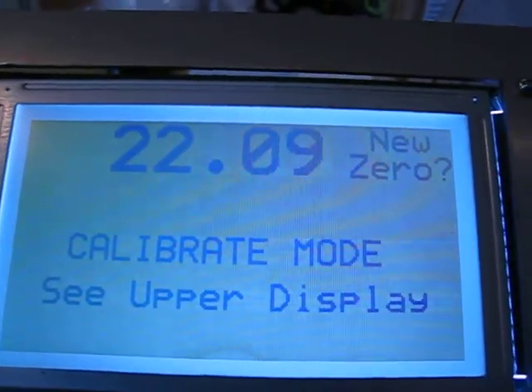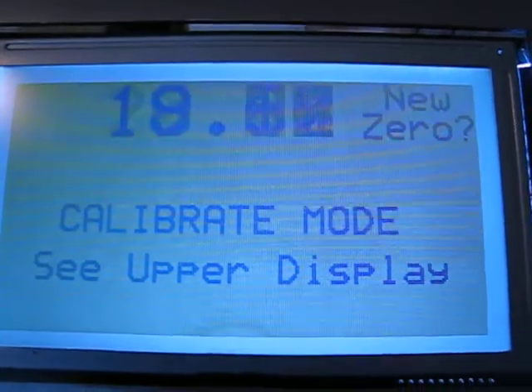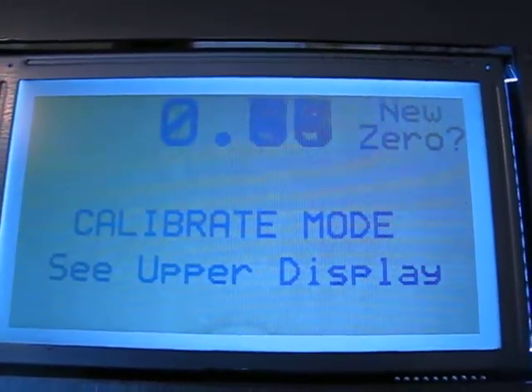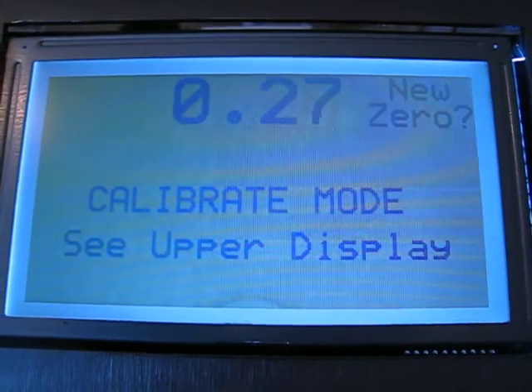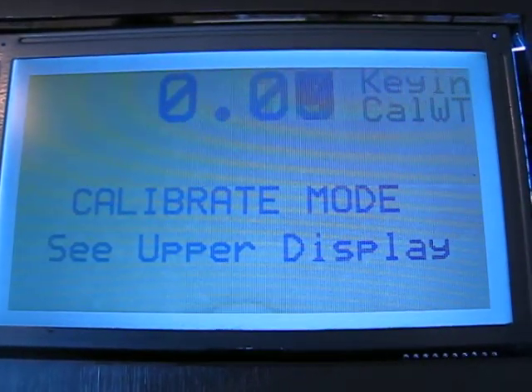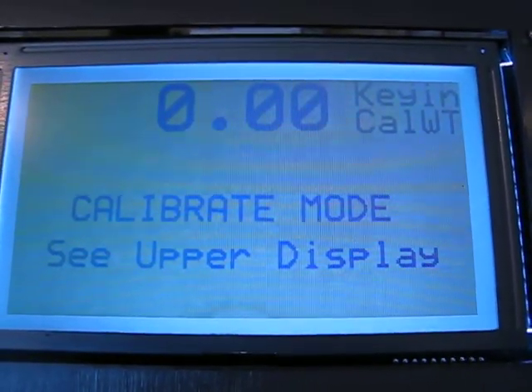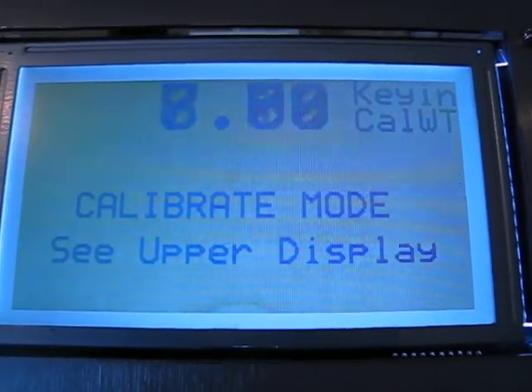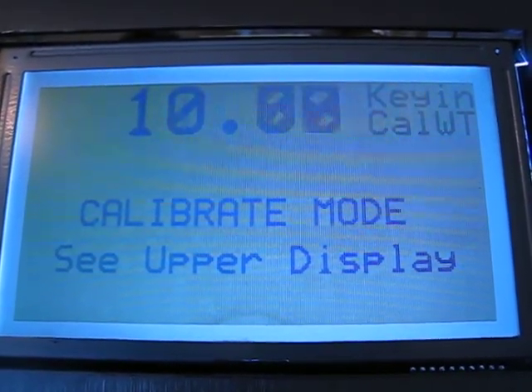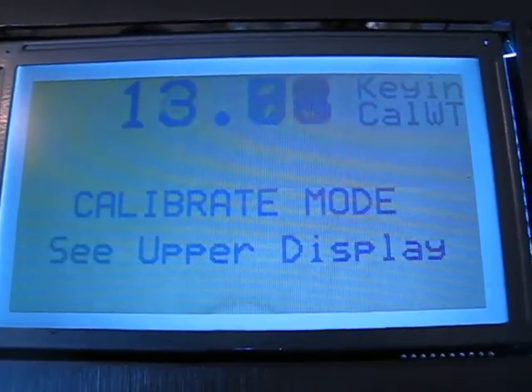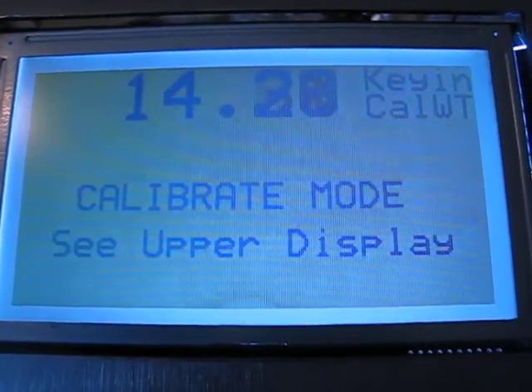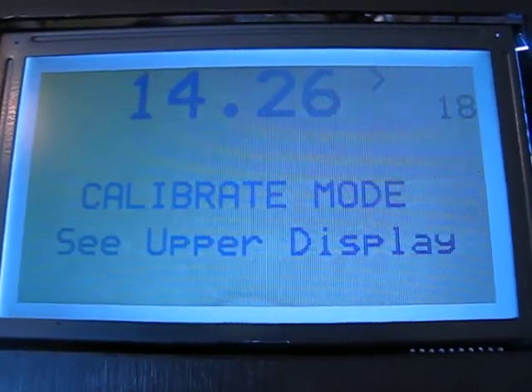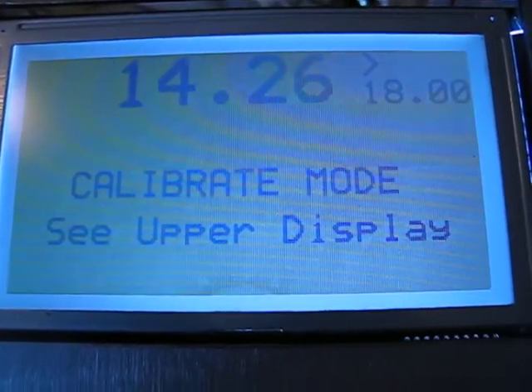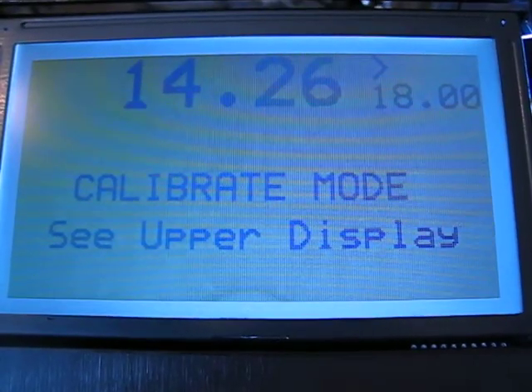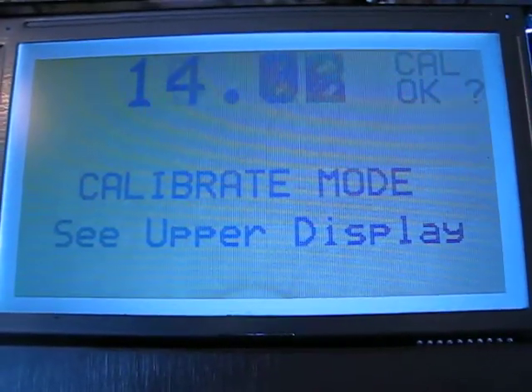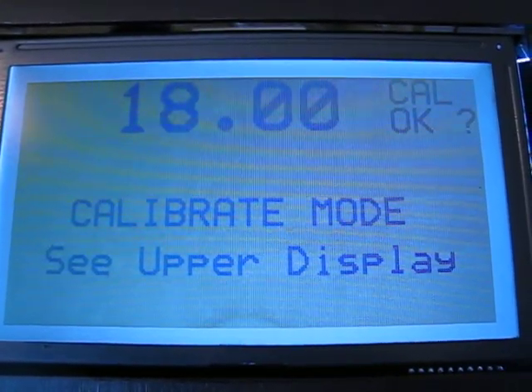So it's asking us if we want to do a new zero calibration. So we would hit enter, we would say yes. Now at this point we would hang our test weights on the scale, and let's say our test weights were 18 kilos. So we would hang the weights on the scale. We would enter our test weight value of 18 kilos and we would press enter. It'll now do its span calibration.